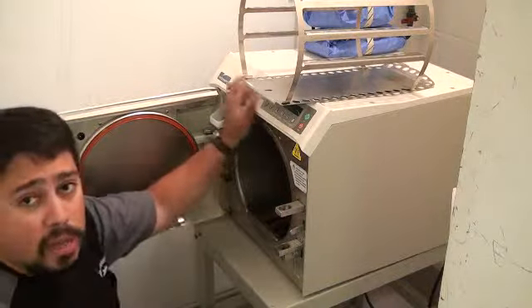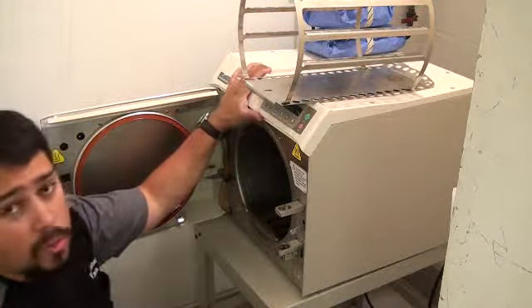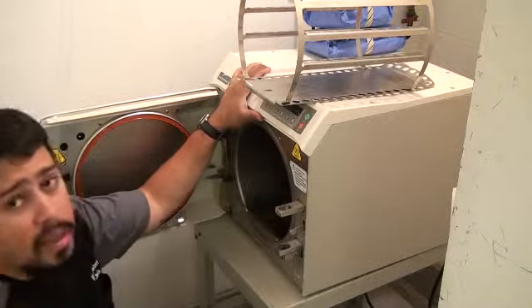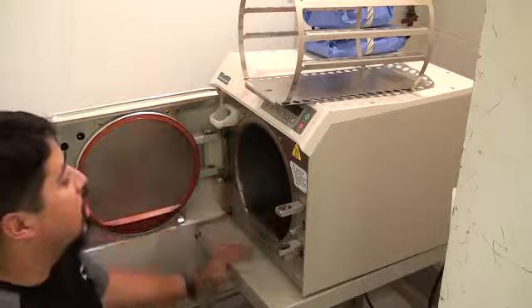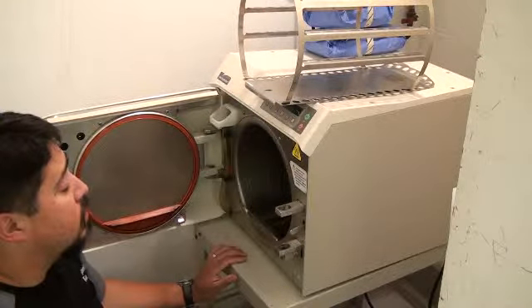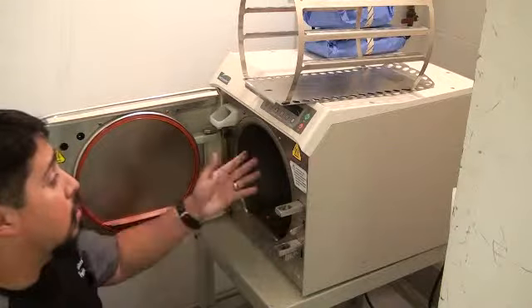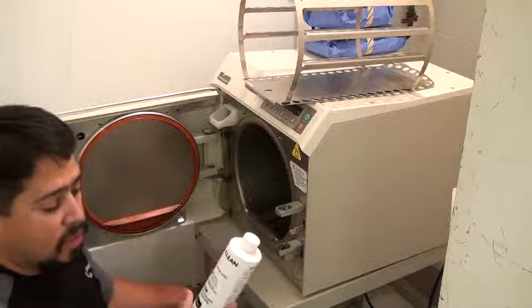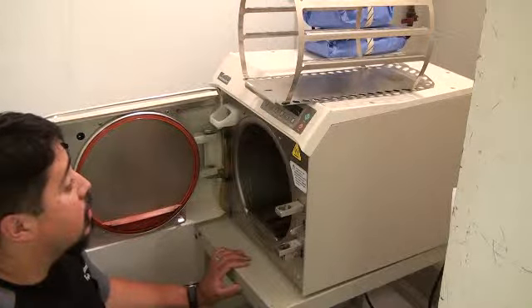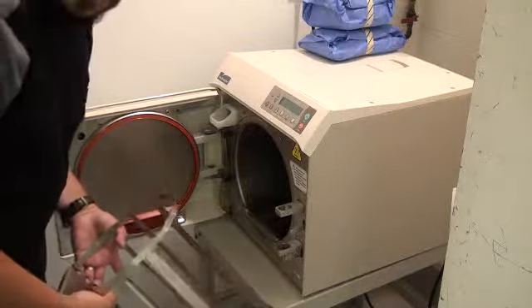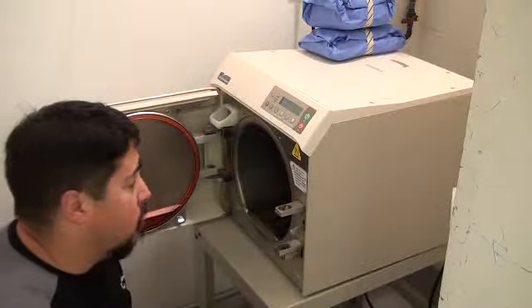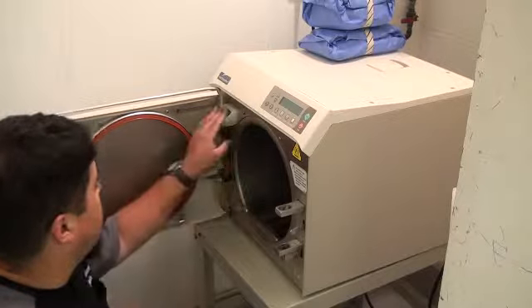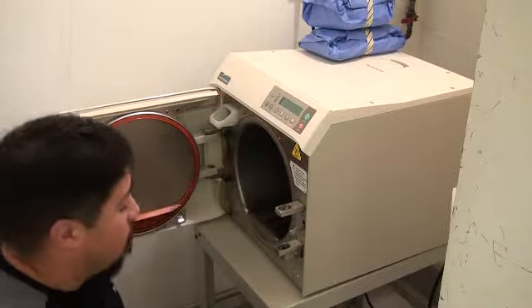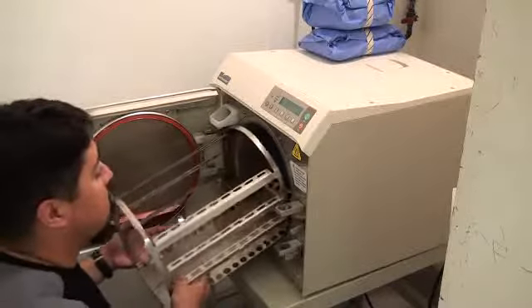Not only is there a weekly reminder, but every 4 weeks, instead of a weekly reminder, you get a monthly reminder to do a more intense cleaning, which involves going through a couple cycles of sterilizing the chamber empty with water and Speed Clean from Midmark. Everything will be put back in after everything is cleaned and sterilized. You will not wash, but you will wipe everything down with distilled water, and then refill the tank again through here with distilled water. The little filters go back in place.